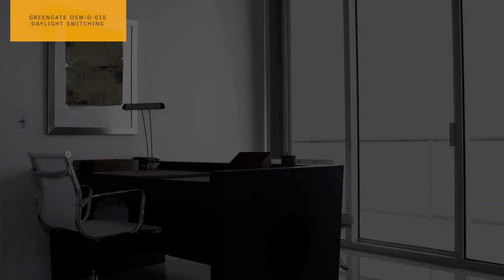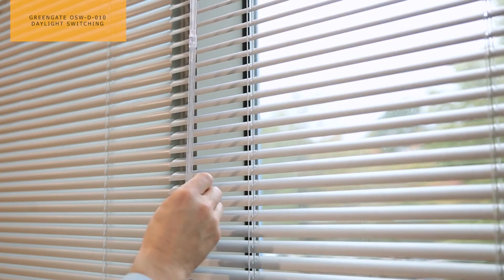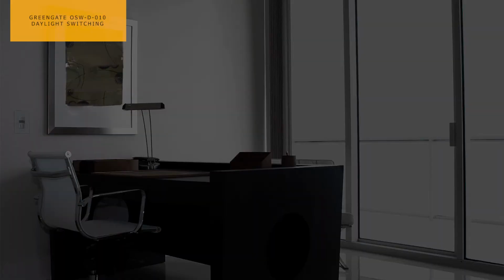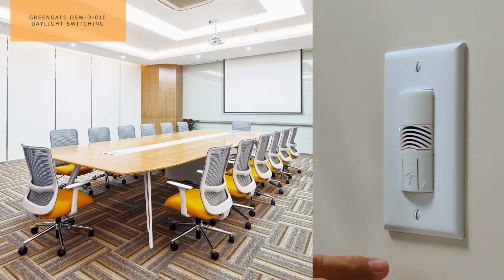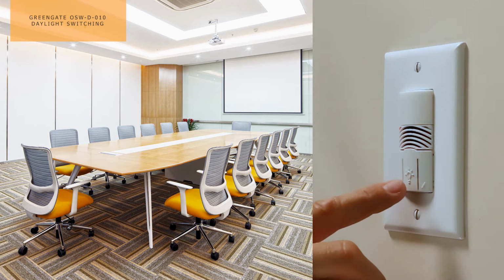Calibrate the sensor for proper operation. This should be done when there is little natural light in the space. Ideally, calibrate the sensor in the evening by using blinds to block daylight contribution. Make sure that the sensor has an unobstructed view of the space. First, turn the lighting on and raise it to its highest level.